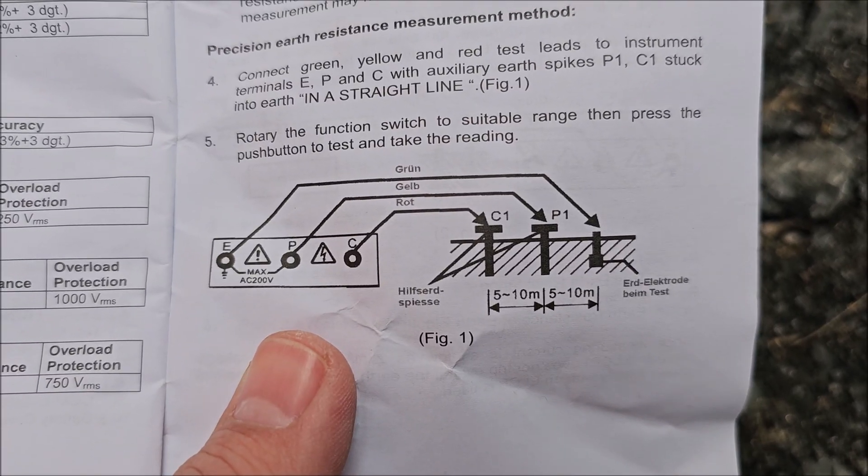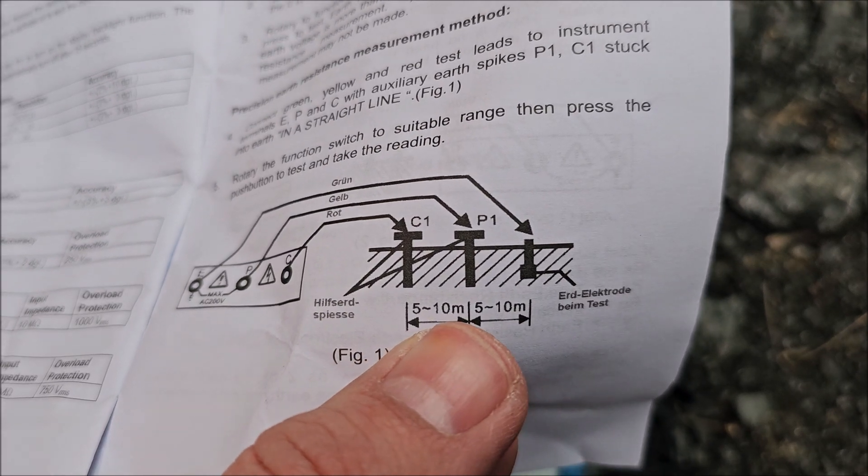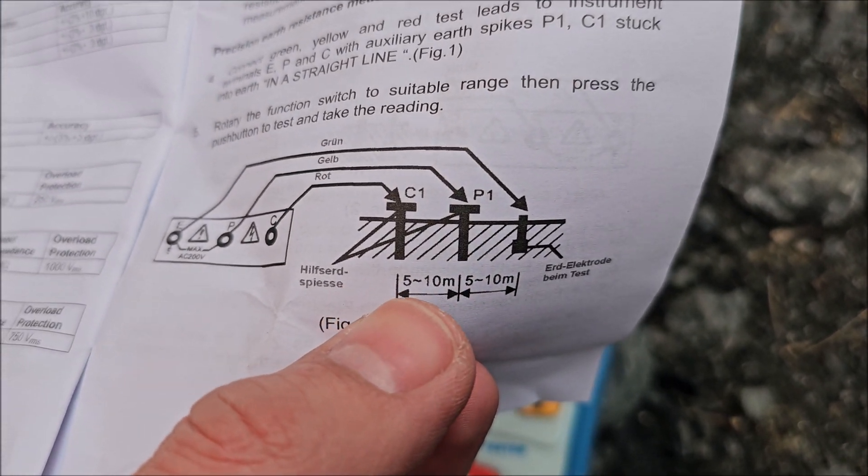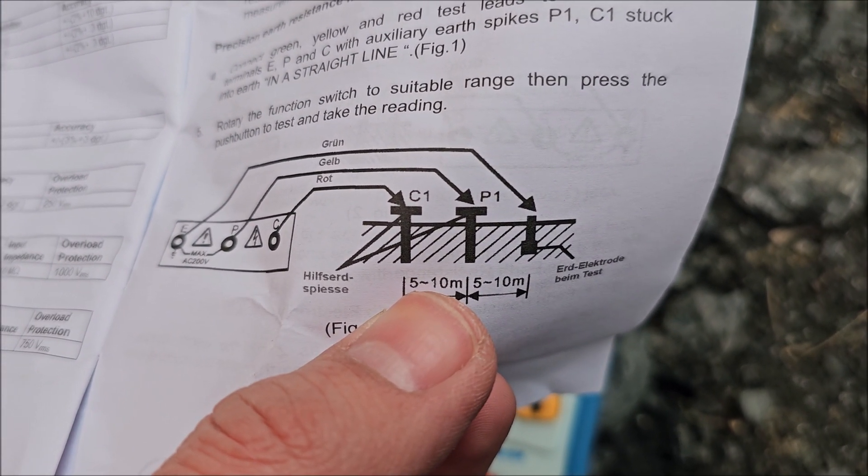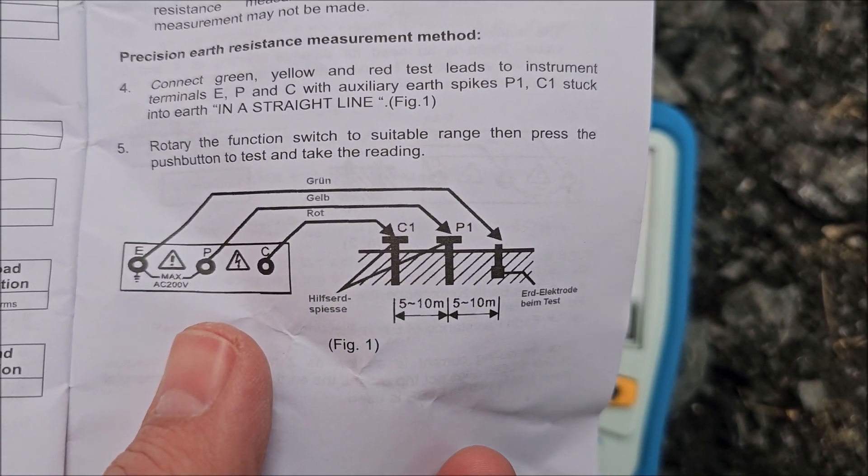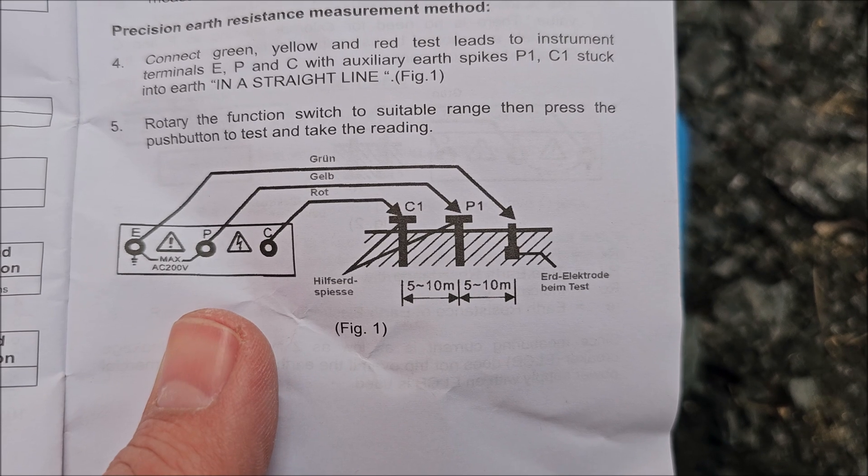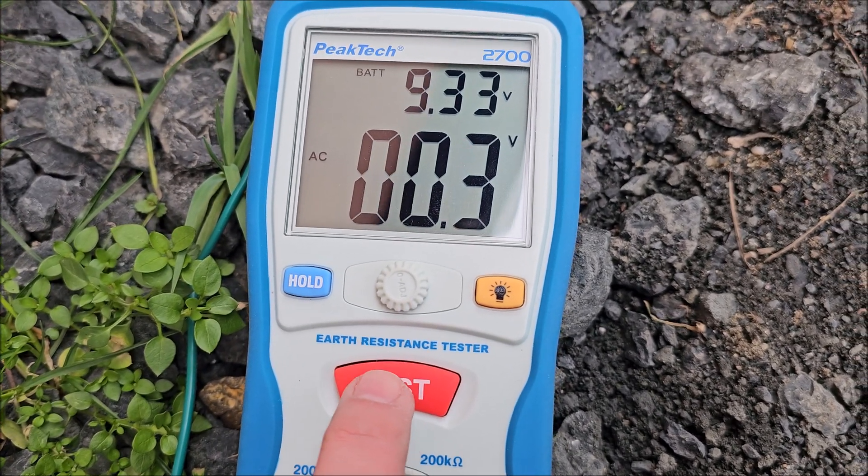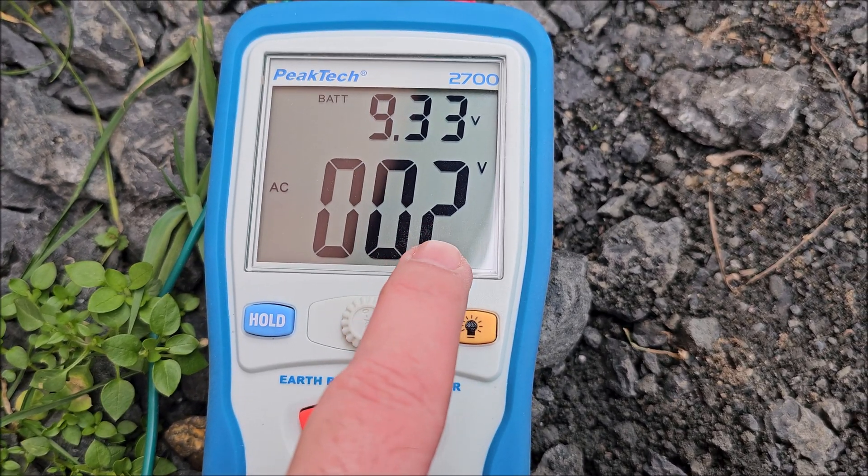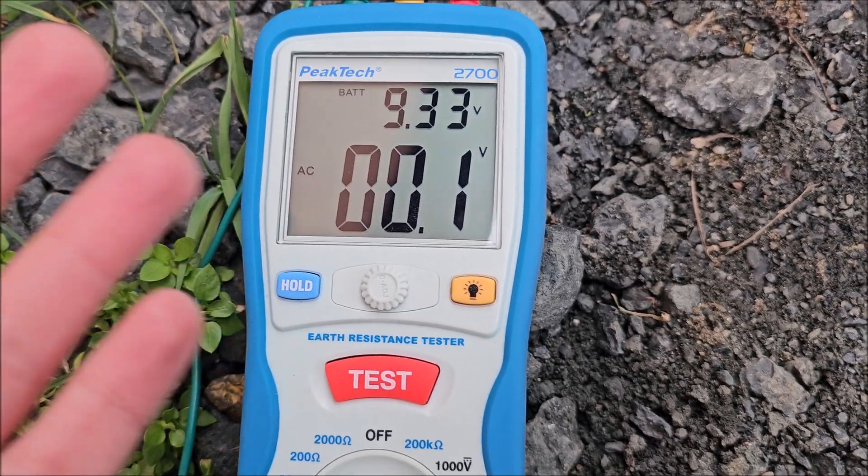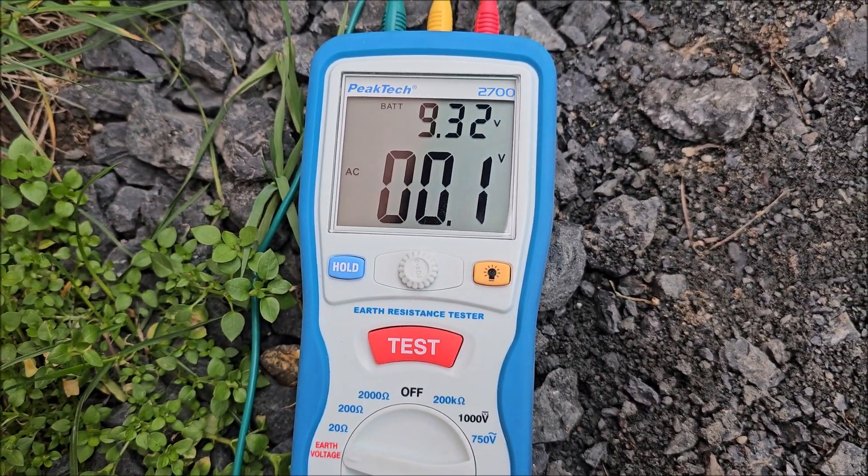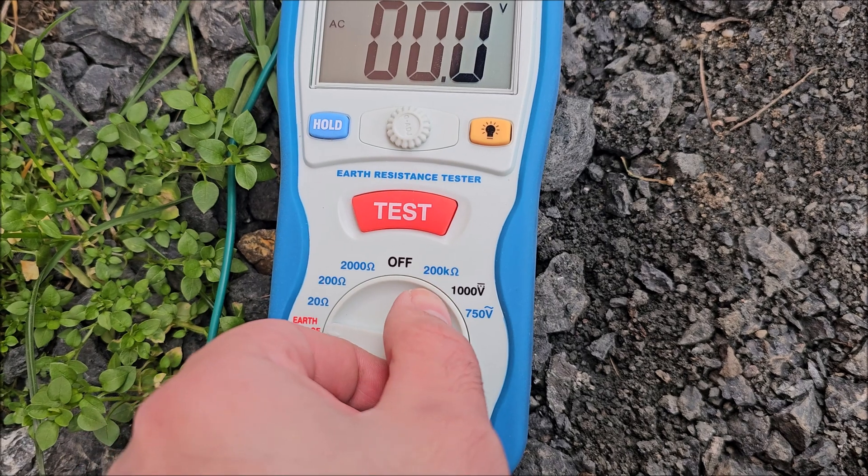Just want to mention the first test that I did was almost at 10 meters, so now I moved them closer. We are at about six meters between electrodes. I want to see what that changes in terms of reading. First again, earth voltage, almost nothing.